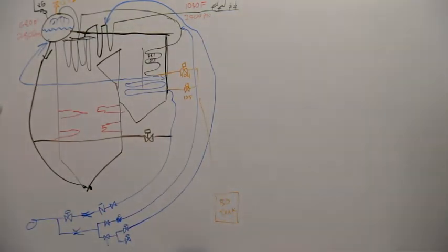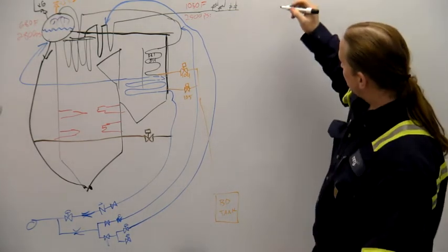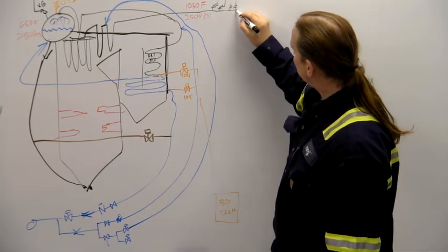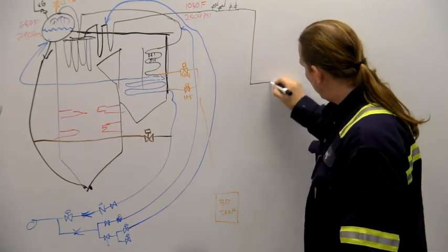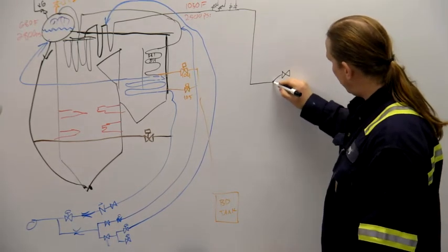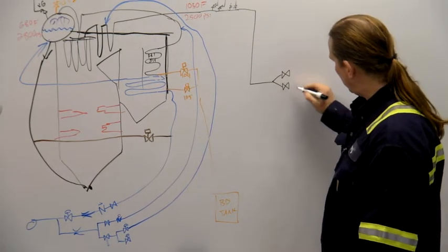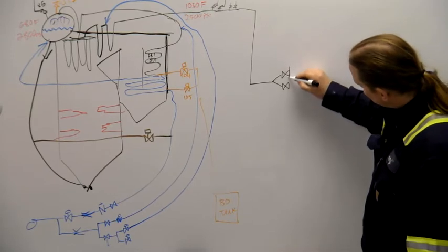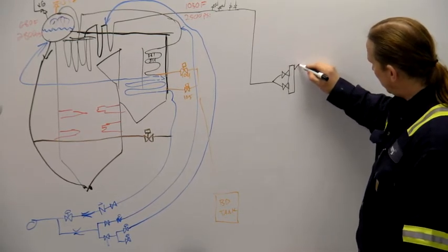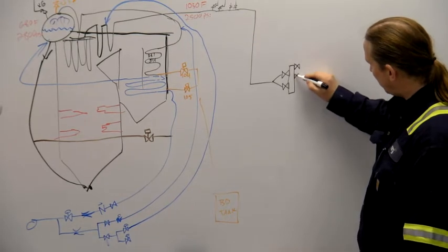Alright, so now we're going to get the steam through the turbine and then back to the feedwater system. This main steam header runs down and splits off to two main steam stop valves, and those discharge to a common steam chest. Then there are four control valves coming off of that.